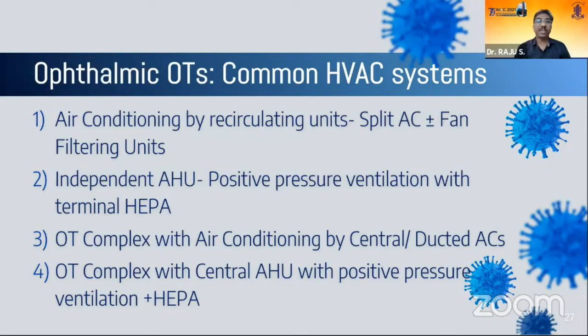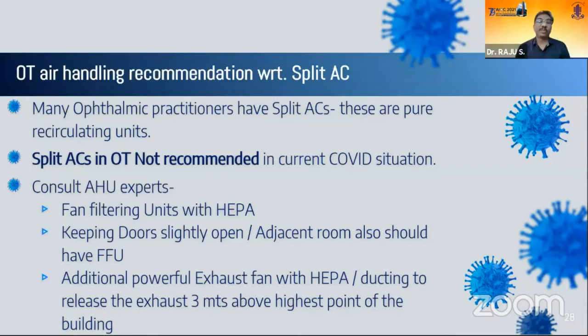As far as the split ACs are concerned, this is not recommended in the current COVID situation. However, most of us will be forced to use these systems. So we can improve this system by adding a fan filtering unit with HEPA. Keep the door slightly open, or the adjacent room should also have a fan filtering unit. An additional powerful exhaust fan with HEPA can also be used when you are using split ACs.